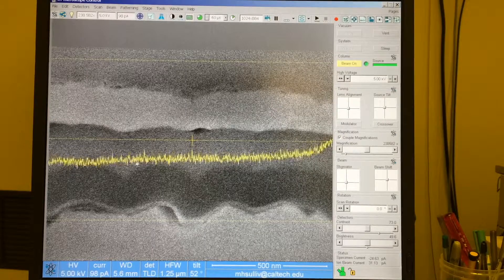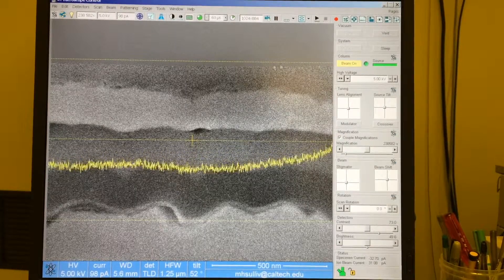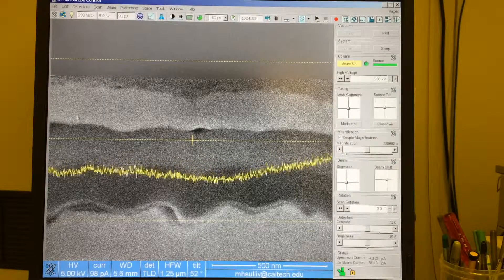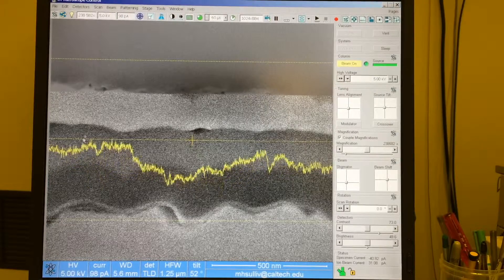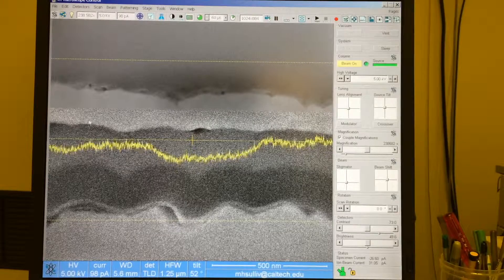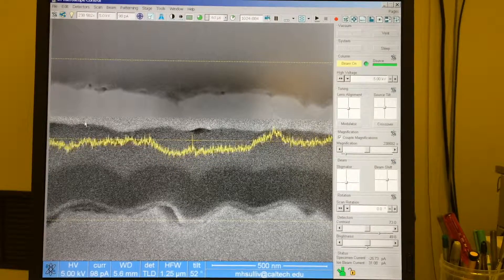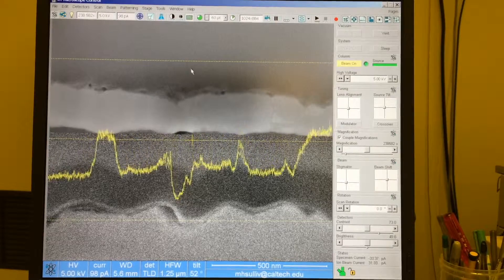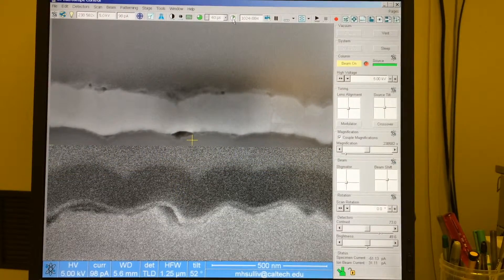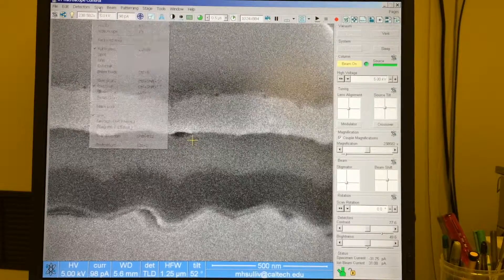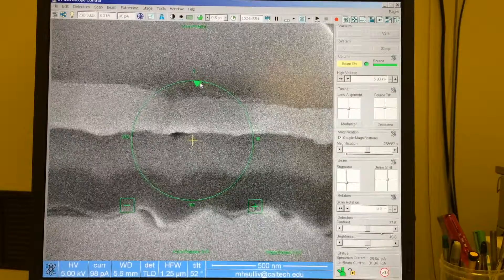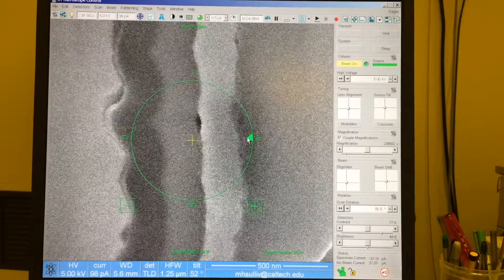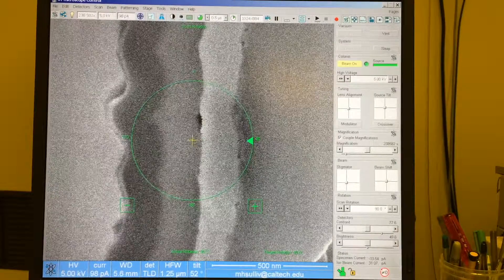This is showing me the gray levels as a function of the beam position along the x-axis. And as it scans over my image, we'll see as it goes into this lighter colored layer, my video scope increases. So this is not really an ideal way to adjust the video scope when the beam is scanning parallel to all of my layers. So instead, what I'm going to do is turn off the video scope, go back to a shorter dwell time, and I'm going to scan and rotate the image. So this just rotates the beam. I can grab this and go around 90 degrees. You can also click the 90 to get exactly at 90.